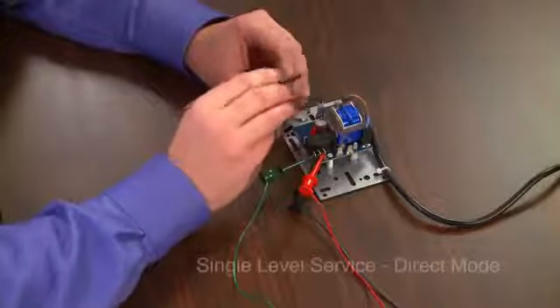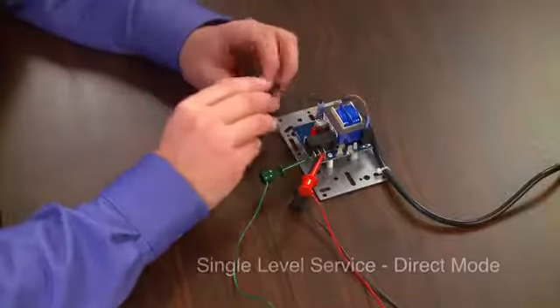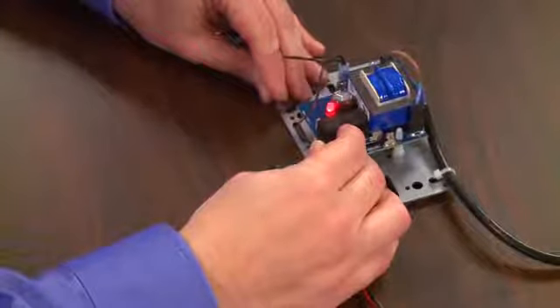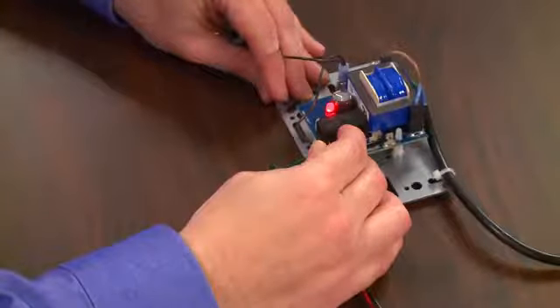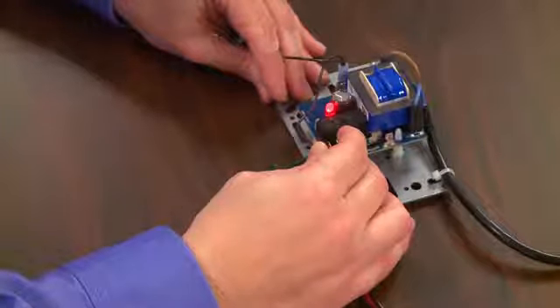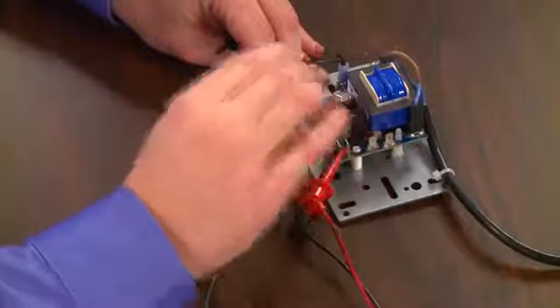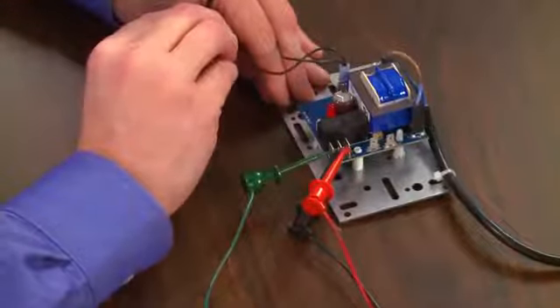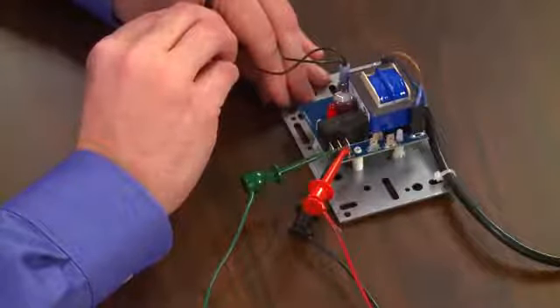We take our jumper from the ground reference probe connection to our high probe connection and as I make that contact the LED came on and the relay is energized simulating that the probe is wet. Probe becomes dry and take that contact off. You notice the LED turns off and the relay de-energizes.